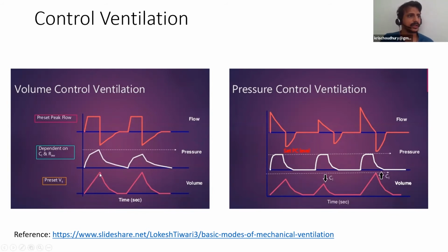And once one tidal volume is met, it allows the patient to exhale out, and again the tidal volume goes up, and then again it allows the patient to exhale out. In pressure control ventilation as well, you can see the same thing happens, but here your pressure is always constant, whatever the doctor has set, but the volume keeps changing. The tidal volume that goes into the patient keeps changing.